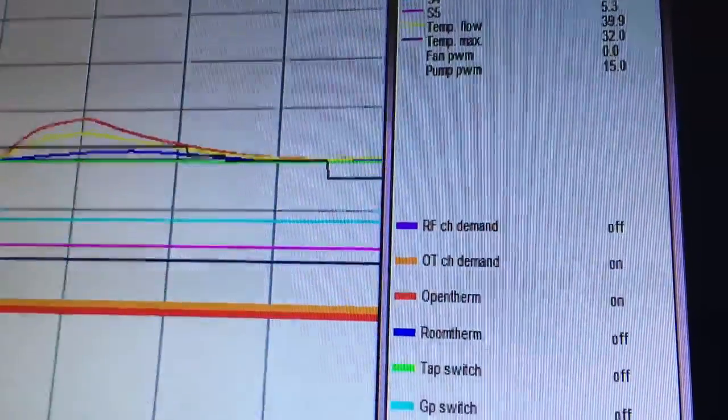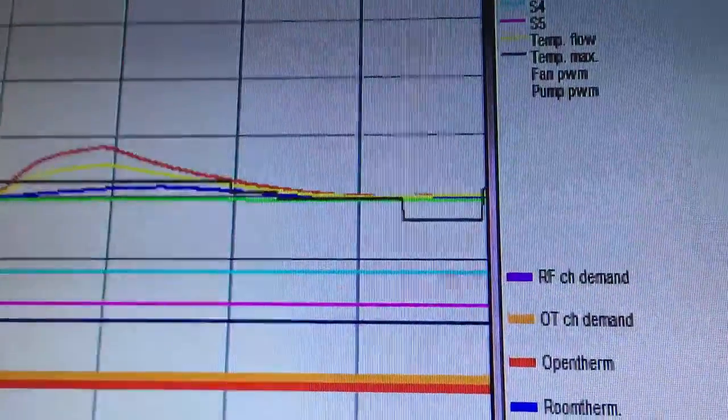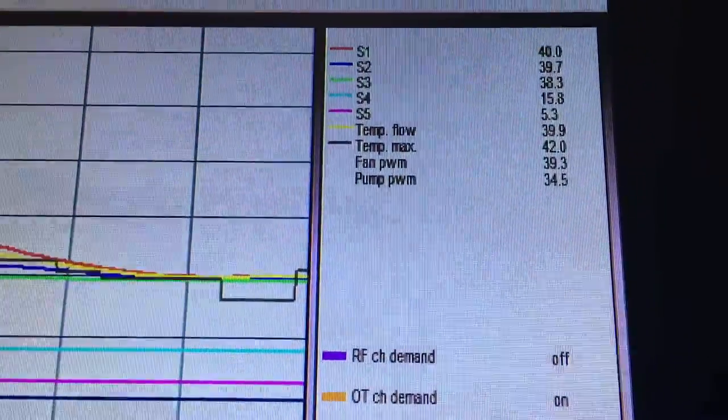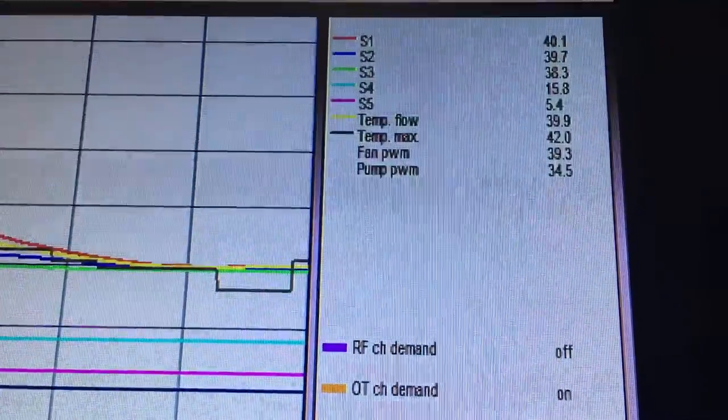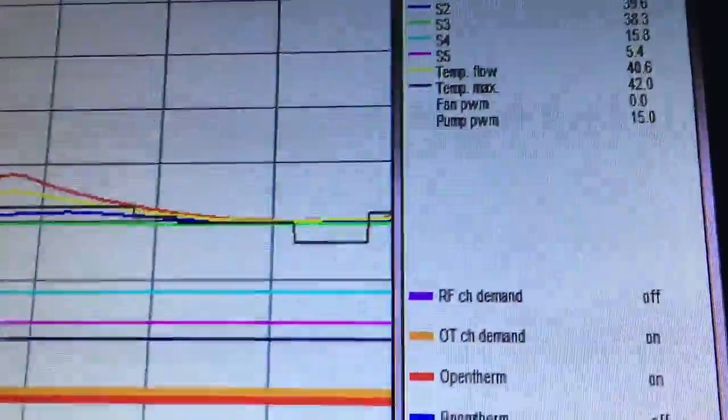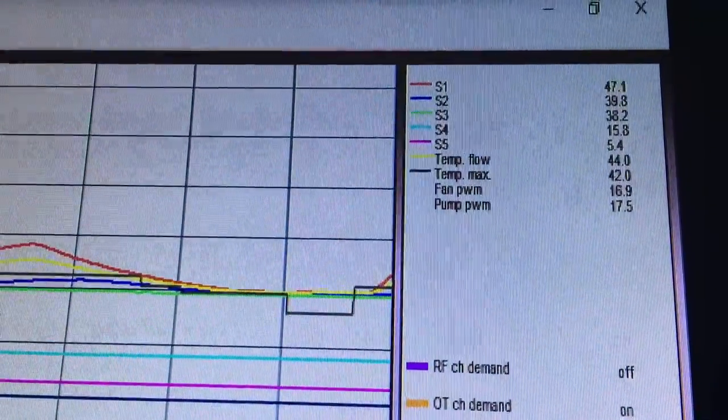So if I put that to 19 degrees—so I've just upped the thermostat now to 19 degrees—you look at the black line, which is the control set point. So now you can see the temp max gone up to 42. Okay, and if I up this another degree up to 20 degrees, if you look at the temp max again...